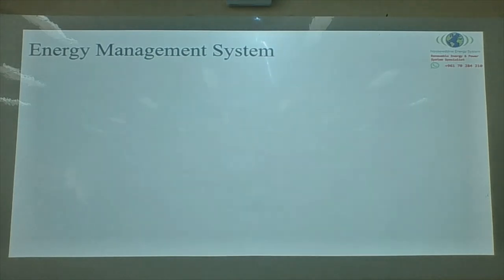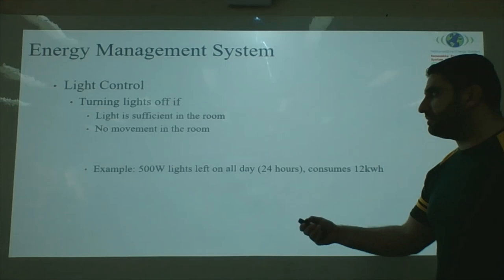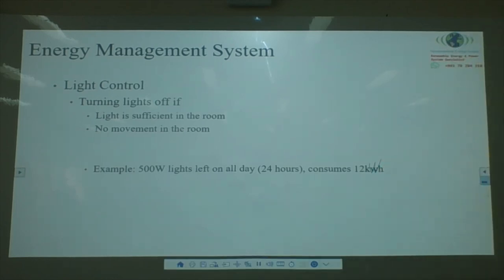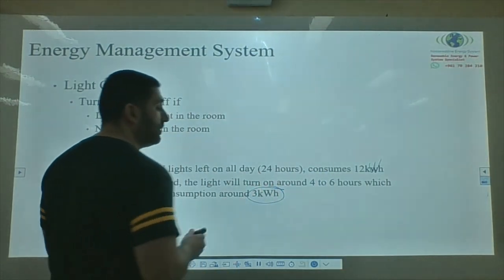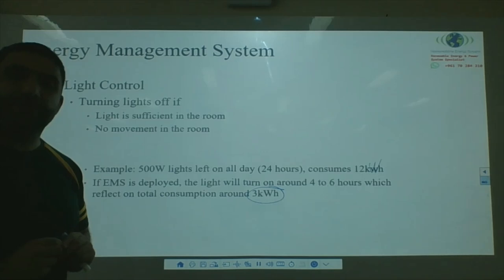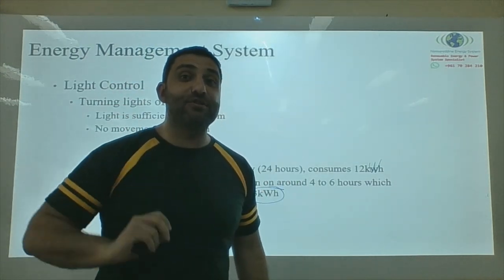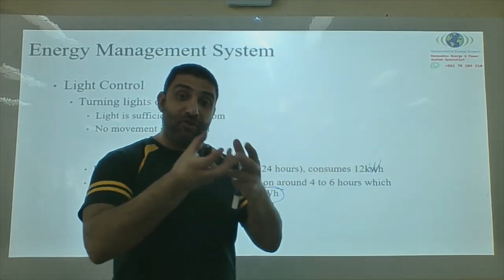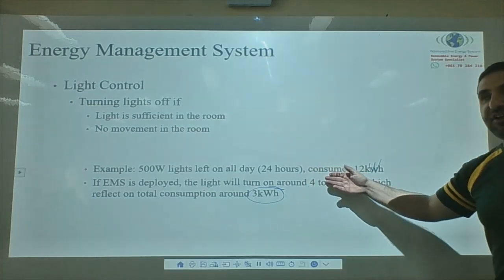A concrete example of EMS savings: a 500 W light left on for 24 hours consumes 12 kWh. With an EMS turning it on for only 4–6 hours, consumption drops to 3 kWh — a 9 kWh saving. Since lights are usually on when there is no sun (battery-powered), at 50% DoD this saves 18 kWh of battery capacity. That reduction is achievable with very cheap light control technology.